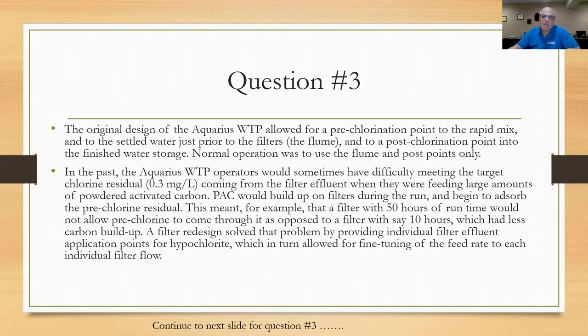For example, the one filter that was in service for like 50 hours would be robbing the chlorine residual, whereas the filter that was only online for 10 hours and hadn't taken in that much activated carbon was putting through a lot more chlorine. We'd get to the point where no chlorine would come through a filter once it was in 70, 80 hours. Now a filter redesign has solved that problem. Recently, well about eight years ago, they went through a filter redesign that provided individual filter effluent application points for the hypochlorite. They can feed hypochlorite to each individual filter effluent based on the flow coming through the filter and the need for chlorine. They don't put chlorine into a common point for disinfection into Clearwell now. Now they do it coming out of each individual filter, which is a much better design for them.